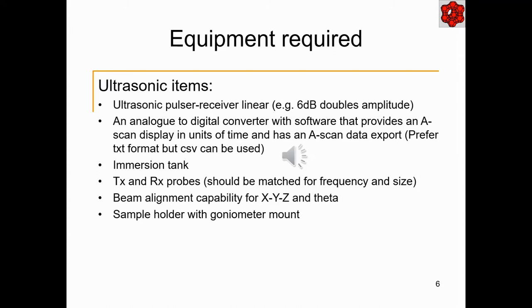The preferred method is to use an immersion setup. This will require an immersion tank and transmit and receive probes with matched frequency and size. The tank has to be long enough to ensure that the sample is in the far field of the transmitter. This usually means using small element sizes unless you have a large tank. There should be alignment capability for x, y, z and theta motion, and the sample holder with a goniometer mount.